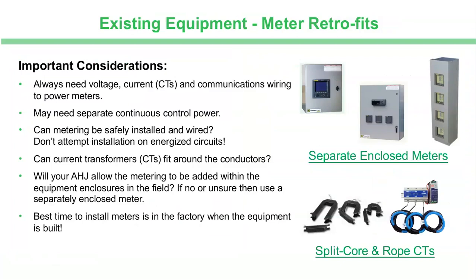So a quick note about retrofit. Showed you a picture there of the new equipment, but when you're retrofitting, there's three considerations that every meter is going to involve if it's part of a power monitoring system. You're going to need voltage to measure from the circuit being monitored. You're going to need current inputs, which normally, almost always will involve current transformers or CTs. And then you need communication so that you can remotely be able to read and acquire all of the information being captured by that meter.